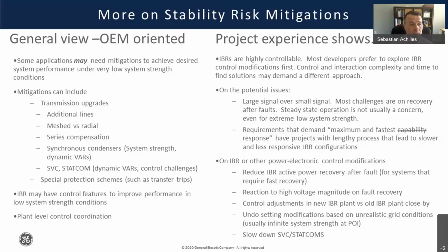Doing something about it could be related to transmission upgrades, usually not the preferred option. You could add additional lines to make the system stronger. You can try to go for a meshed approach where you mesh the system so that N-1 contingencies don't result in such a significant reduction of system strength. The use of series compensation is quite common in some markets around the world. Synchronous condenser was mentioned, that it solves the system strength. It may create new problems.